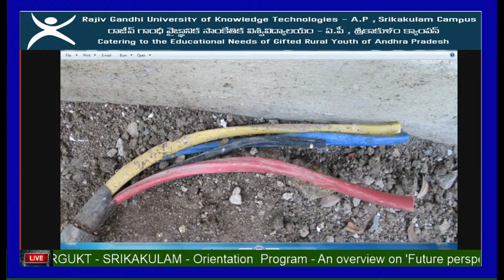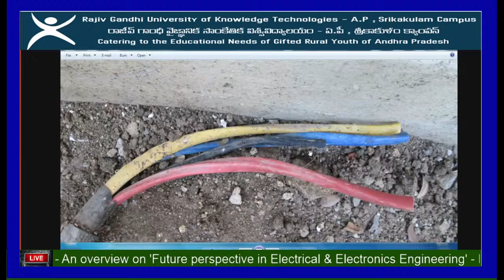Suppose all 3 currents are balanced, the neutral current should be 0. But if you don't get a balanced current, there will be a neutral current. If this neutral current is very high, the neutral voltage gets shifted, and if the shifted voltage is more than 5 to 6 volts, your motherboard is going to get crashed. Especially in rainy season and thundering times, we should be very careful about such things.